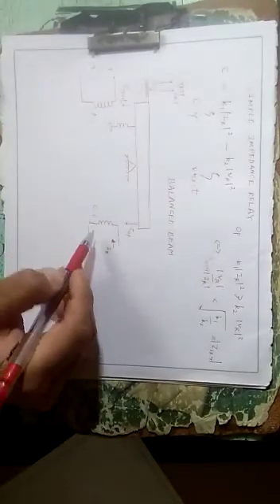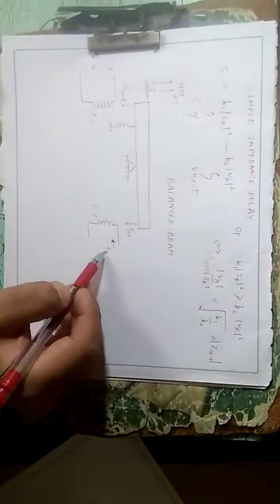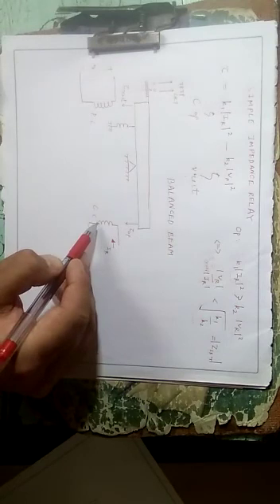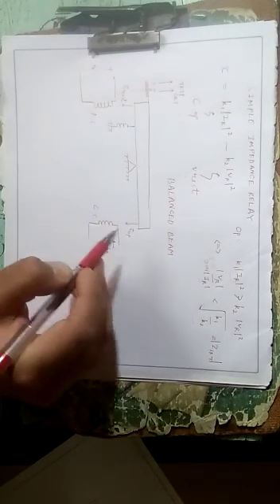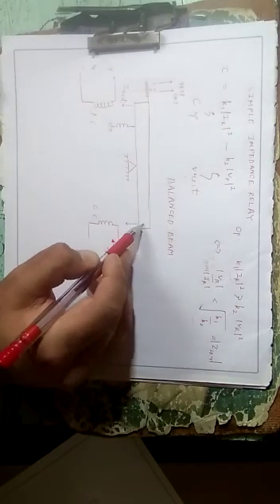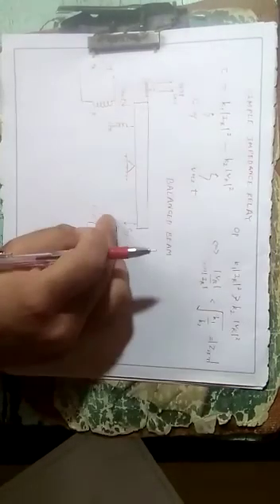It will restrain. Hence here, as you can see, I have written torque restraining. The torque this produces is like this. It is preventing the operation of the trip circuit. The current coil is obviously exactly different. The larger the value of current, the larger the value of flux. The larger the value of flux, the larger is the force of attraction on the iron. The higher is the probability that it will move downwards. अगर ये नीचे जाएगा, ये automatically ऊपर जाएगा. And if it moves upward, this circuit is completed and the circuit breaker operates.